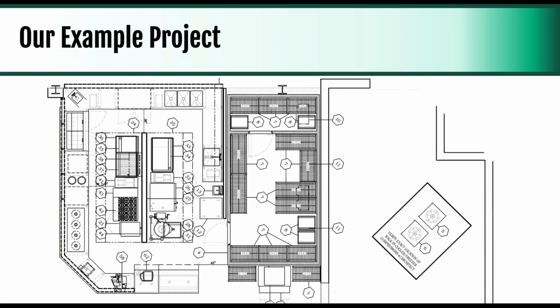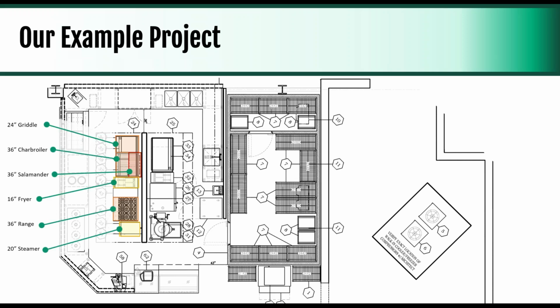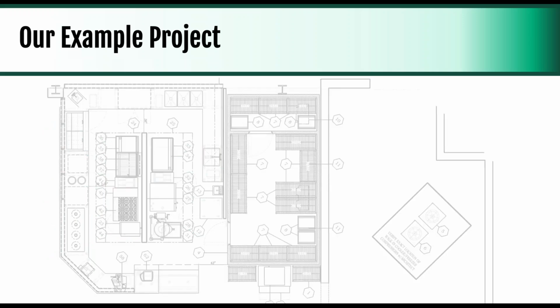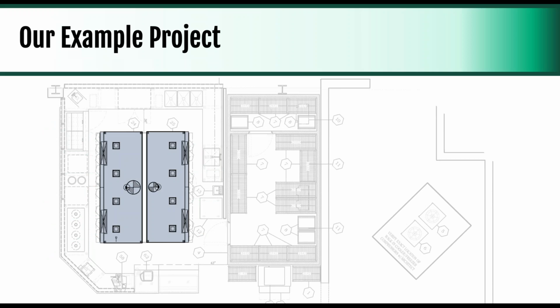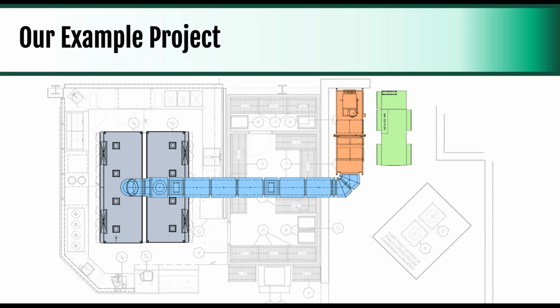So for us, we're looking at an example project, and again, starting with the appliances, we identify everything, get it put into the system, and then based on that, we design our hoods. So this is just a mock-up of the selection, dropped them into place. From that, we've got a KES unit. We could easily just size an exhaust fan as well. KES, sorry if I say so, is our exhaust filtration unit, or PCU. Some people call them scrubbers, whatever you have. It just cleans the air before it gets exhausted, removes the grease. Then we design a makeup air unit to bring that fresh air in. The last thing we typically look at is also engineered duct run. That provides a good quality product, typically saves some space versus field welders as well.